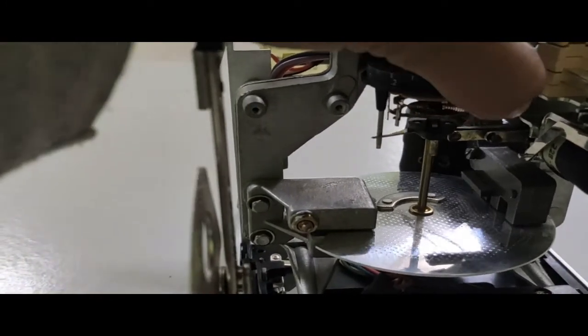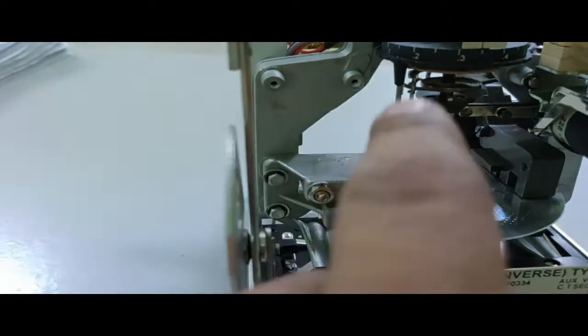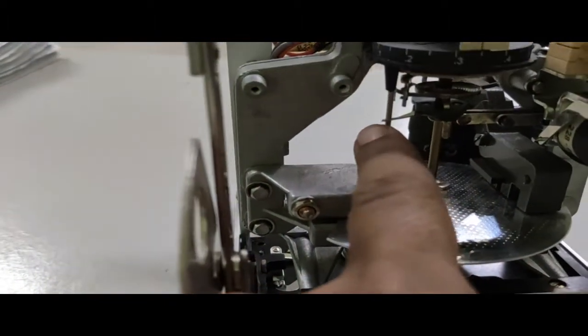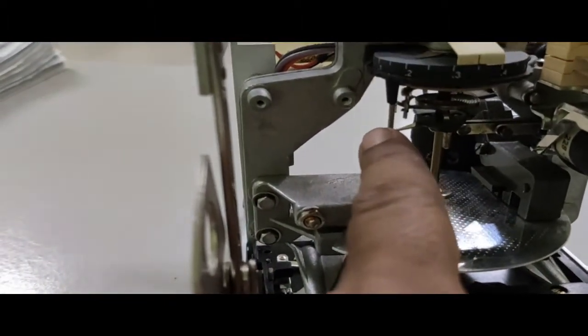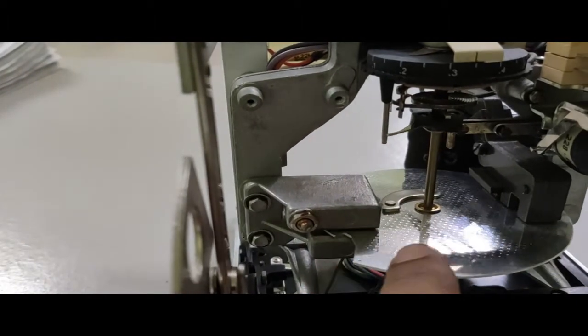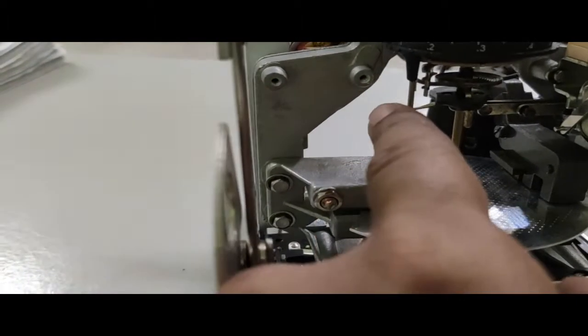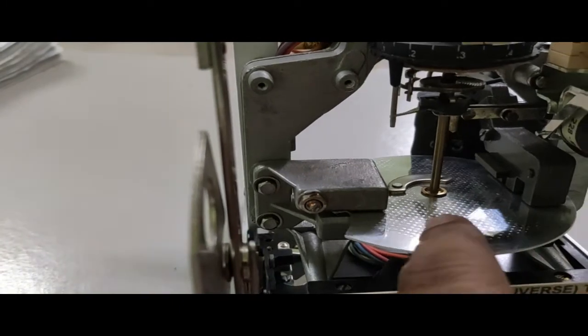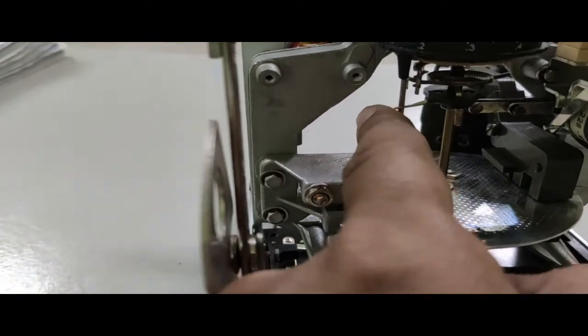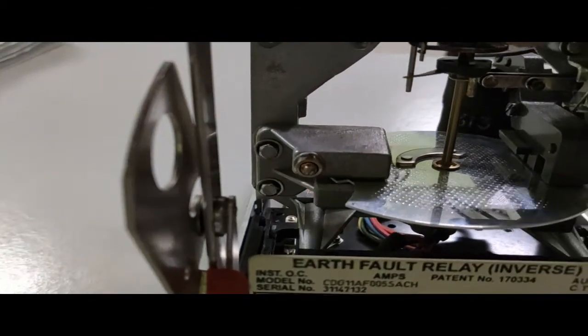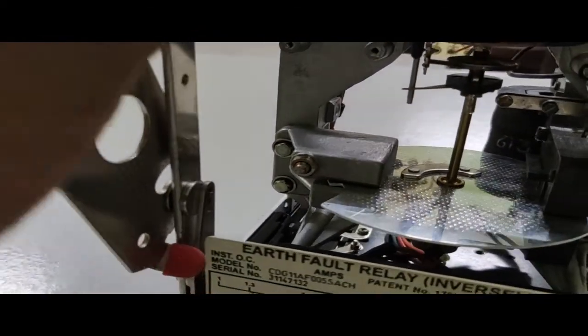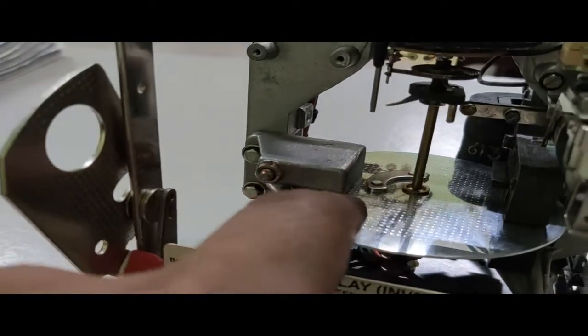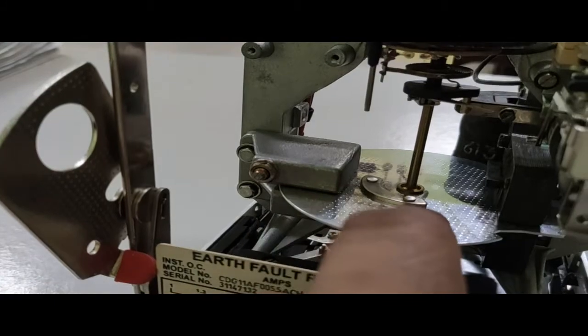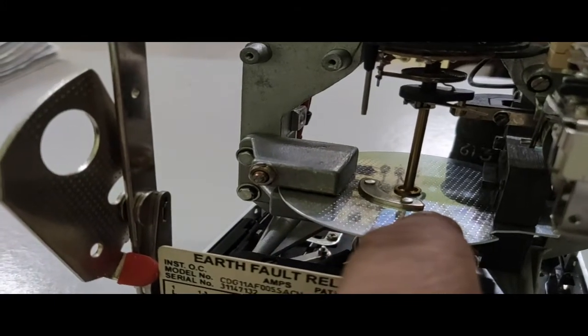So this is a dial, and you see this dial contains some projected parts here, and another thing is here. Now this one is actually the backstop. Due to that arrangement the disc is not able to move further beyond that point because it is connected here. This adjusts the distance between that part and the ultimate tripping signal. So in that moment the disc needs to rotate only this distance to trip the relay or generate the trip signal.